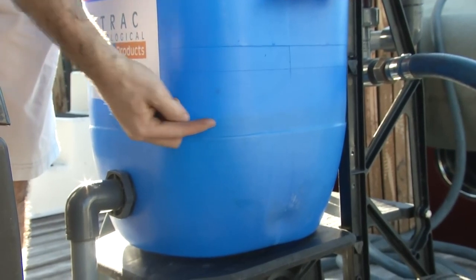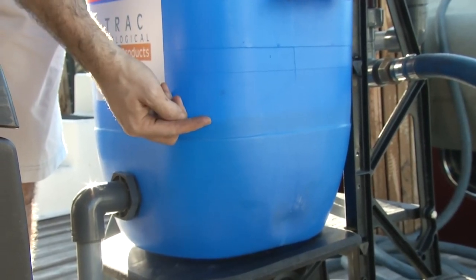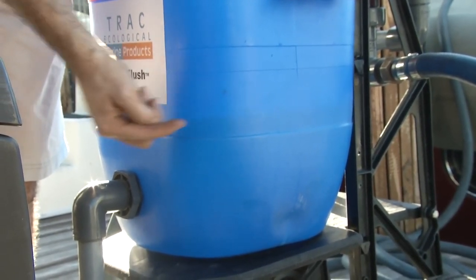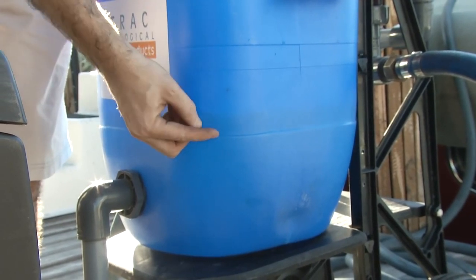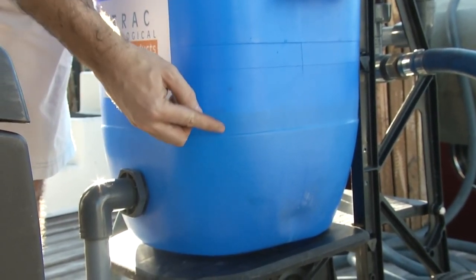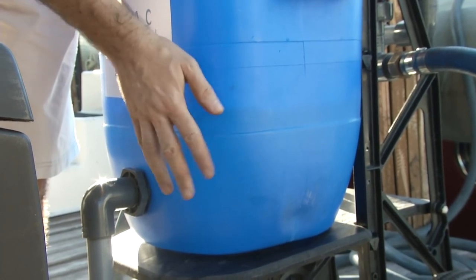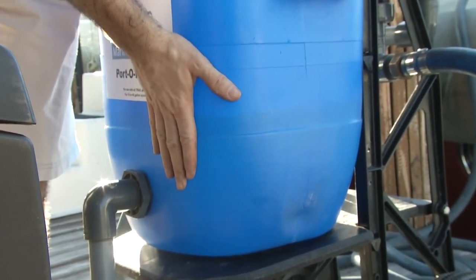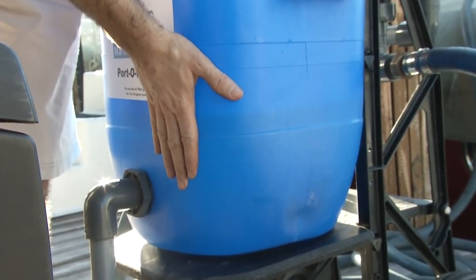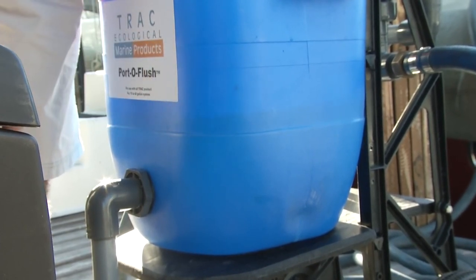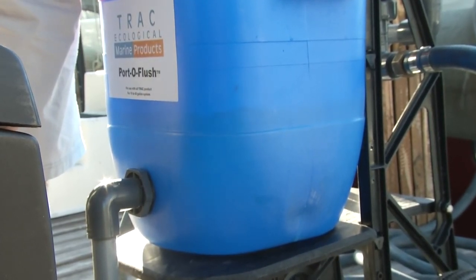One thing I like to do is note the level on the side of the tank, a reference you can remember. If you keep an eye on this for a couple minutes and notice the level hasn't dropped, you can tell just from standing out here that there are no leaks in the system, since you're not losing any more water. At this point, it tells me that we're ready to introduce the Barnacle Buster concentrate into the solution.